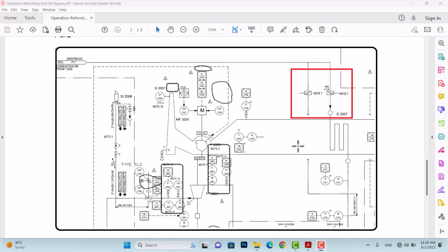And when its density changes, the volumetric flow rate also changes. And since the pressure controller was in automatic mode, unfortunately, at that time this controller was unable to cope with the situation, and because of this the draft pressure got out of range.